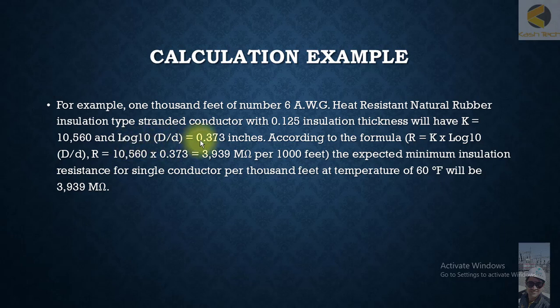And log of 10 (D/d) will be equal to 0.373 inches. According to formula R equals K times log of 10 (D/d), where R equals 10,560 times 0.373, that is equal to 3,939 megaohms per 1000 feet.